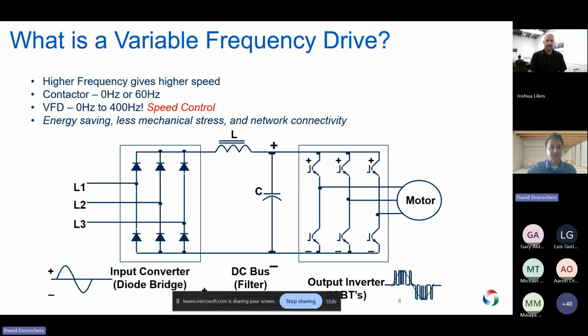Typically with fans and pumps, you're going to be able to control flow rate this way. So the main benefits here are energy savings. You're going to get less mechanical stress by basically using this device as a fancy soft start. And finally, you get network connectivity incorporated into the drive as well. If you haven't seen it before, this is the general schematic of a VFD. They're very consistent across different manufacturers. Of course, reliability and user interface are going to be the main things that differ.